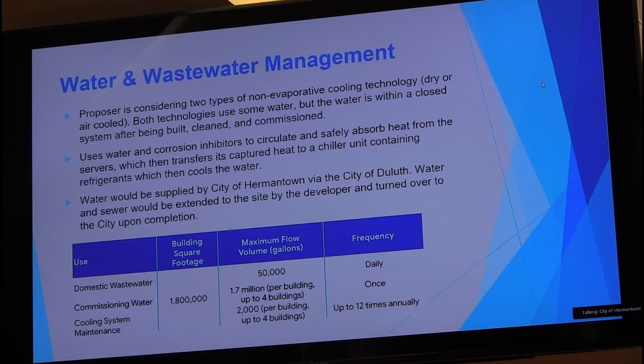We do add corrosion inhibitors and antimicrobial agents to the water, and there's a good reason for that, and that is because we never want to replace that water. So we have facilities that have been operating for years, some over 10 years, where we have not had to replace large volumes of that water. And so by maintaining that and continually monitoring it, we can basically fill up that closed loop system once and not have to continually replenish it.